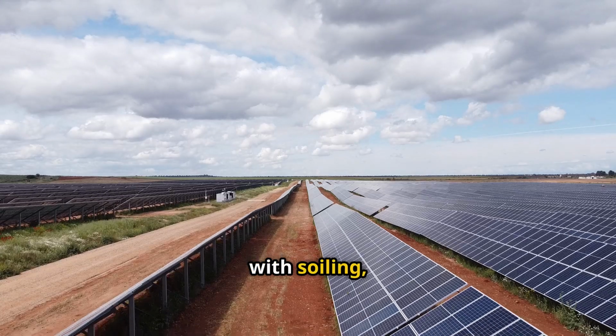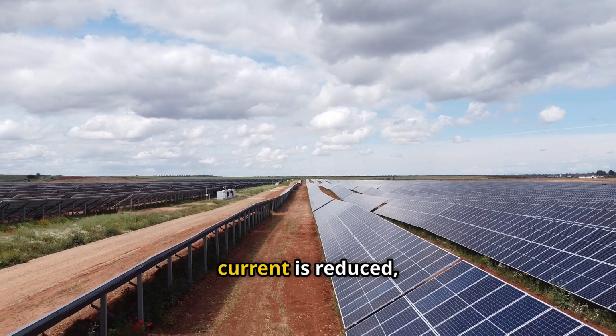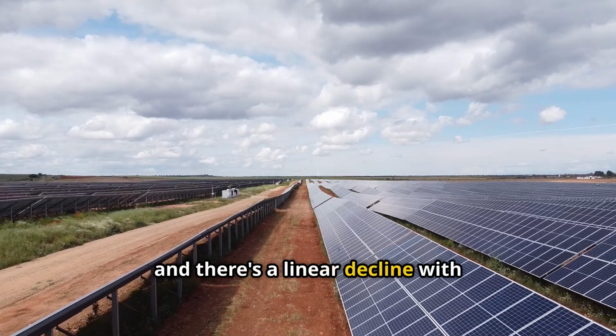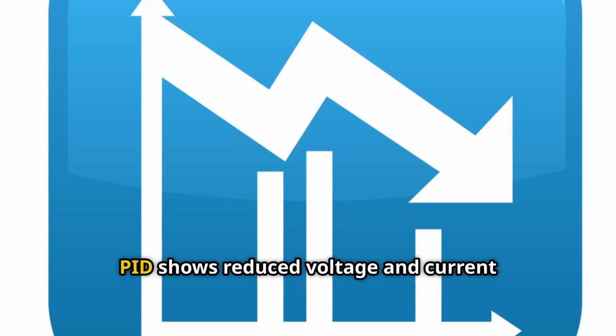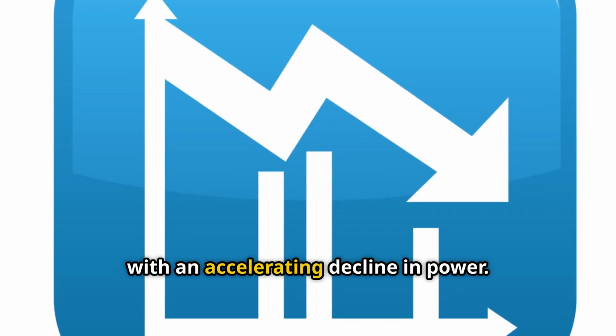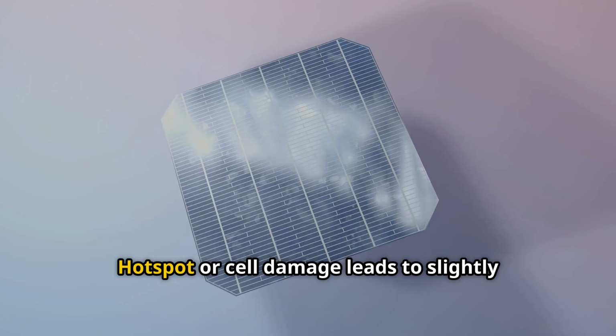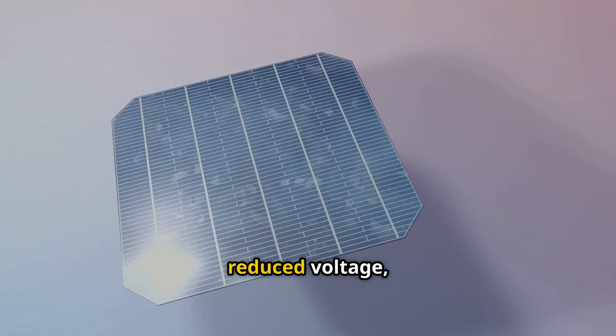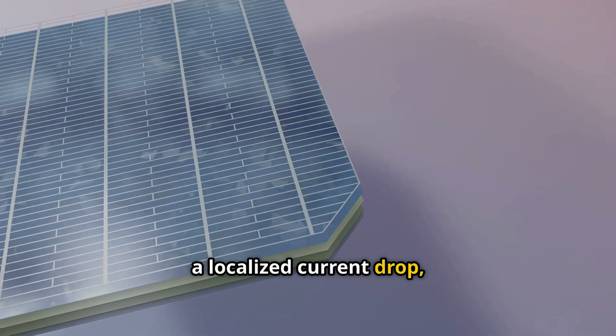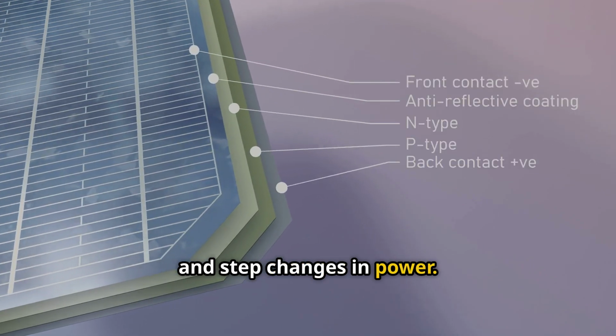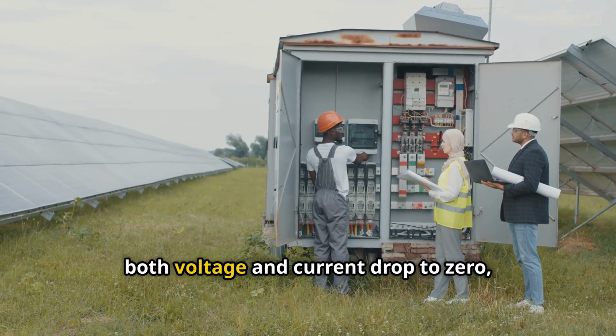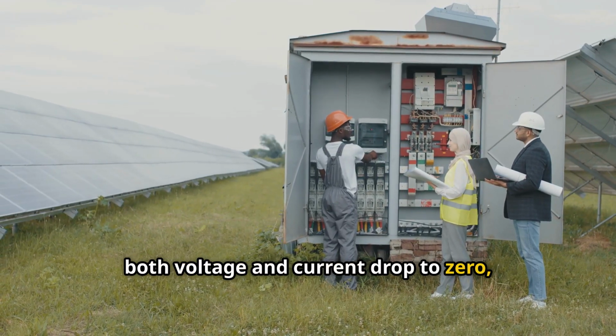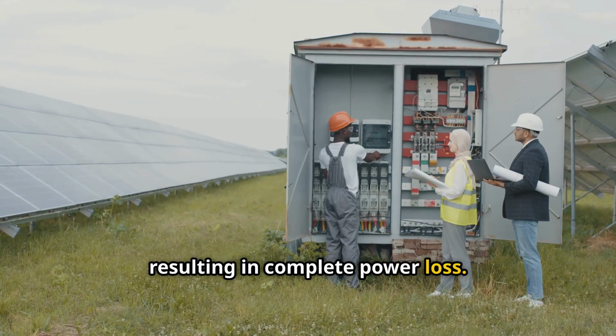For example, with soiling, voltage remains stable, current is reduced, and there's a linear decline with irradiance in power. PID shows reduced voltage and current with an accelerating decline in power. Hotspot or cell damage leads to slightly reduced voltage, a localized current drop, and step changes in power. If a string disconnects, both voltage and current drop to zero, resulting in complete power loss.